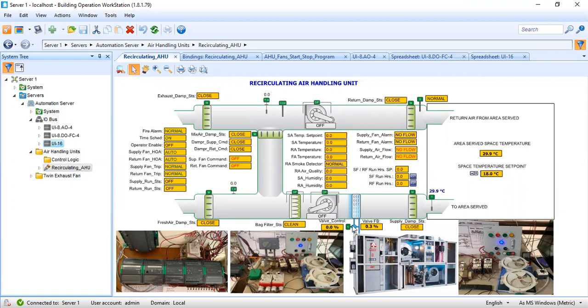Now, the control signal here I set to 0 to 10 volts. This analog output module is capable of giving a 0 to 10 volts control signal or 4 to 20 milliamps. So I selected 0 to 10 volts. This valve actuator will receive 0 to 10 volts DC, and it is configured so that 0 volts is 0% opening and 10 volts is 100% opening.